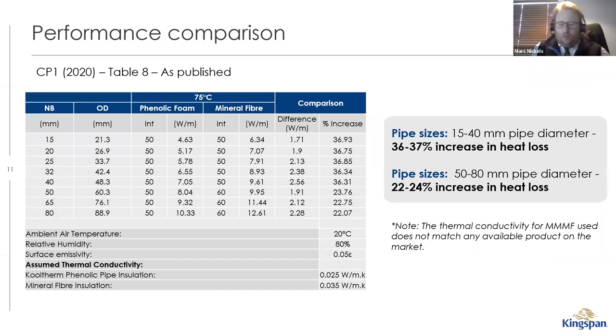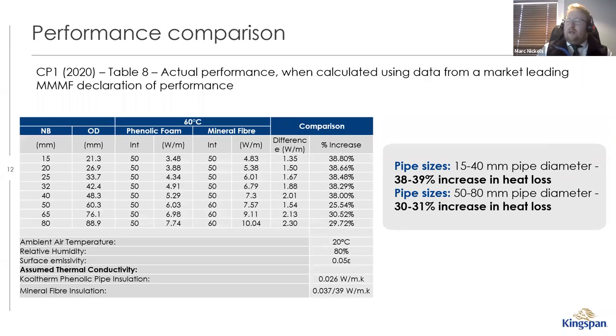Looking at the actual performance impact: in CP1 Table 8 there's a 36–37% performance difference between 50mm phenolic and 50mm mineral wool, and around 22–24% when comparing 50mm phenolic to 60mm mineral wool. When you use actual lambda values at operating temperatures, that difference increases to 38–39% on smaller sizes and 30–31% on larger sizes. It's really important to understand what thicknesses you actually need.